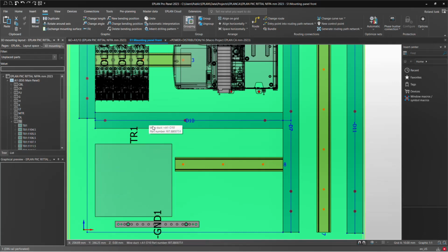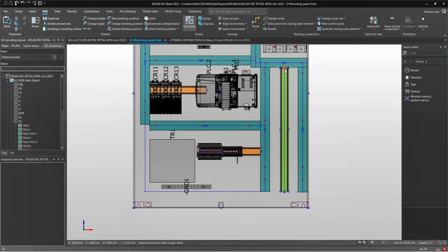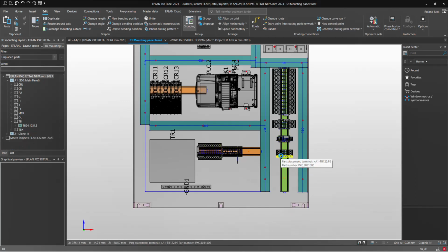Really interesting. Now, of course, in this digital twin, like we said earlier with Phoenix Contact planning, what we did earlier is we added these extra accessories. I mean, it may sound like very, very detailed, but these details about all of these additional accessories, they do add a few millimeters here and there, and they are actually also what makes one terminal or the other terminal actually so-called CSA approved or UL approved, because you can't just have an open-ended connection.